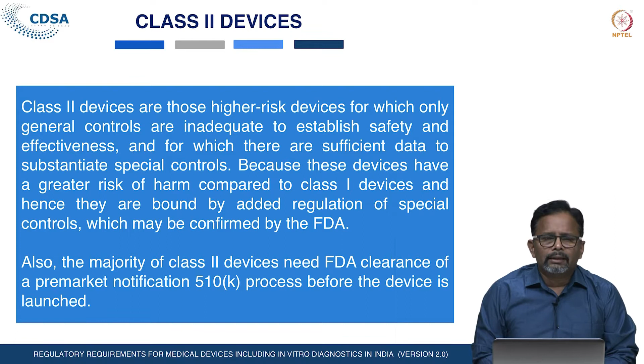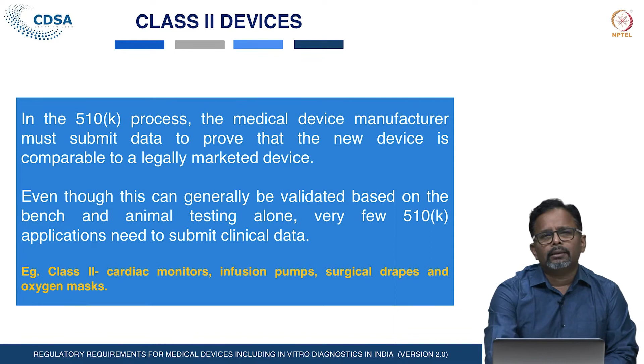In the 510K process, the medical device manufacturers must submit the data to prove that the new device is comparable to the legally marketed devices in the USA. Even though this can generally be validated based on the bench and animal testing alone, certain 510K applications need to submit the clinical data to the FDA for its approval. Examples of class 2 devices in USA are cardiac monitors, infusion pumps, surgical drapes and oxygen masks.